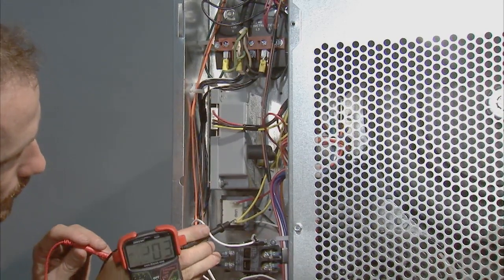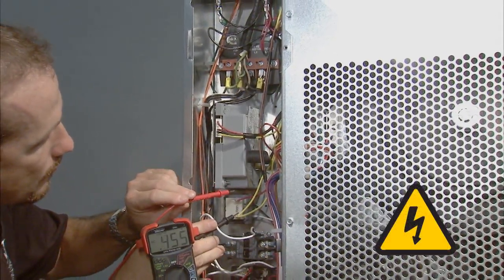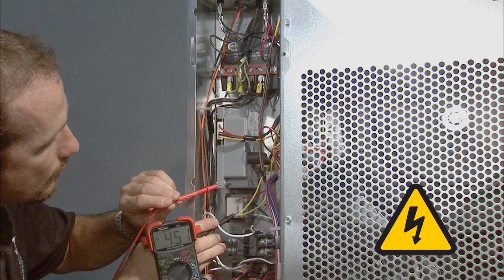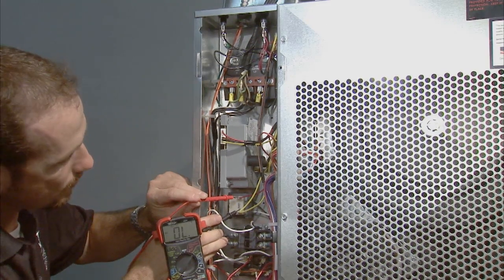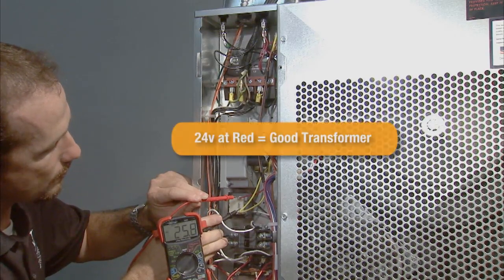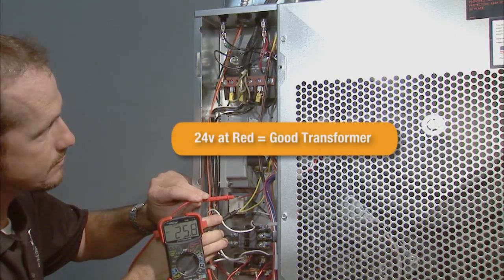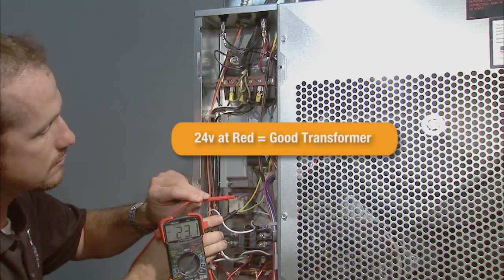The final voltage test will be the low voltage heat circuit. Set the voltmeter for 24 volts AC. The black meter lead will be placed on the yellow neutral wire of the transformer. Now, place the red lead of your meter at the red wire. There should be 24 volts present at the transformer. If 24 volts is not exiting the transformer, replace it.